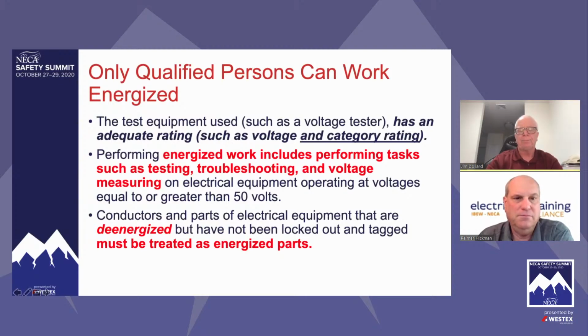Yeah, and Palmer's right. We hear about that, unfortunately, with regularity. Somebody taking a 600 volt test instrument and putting it across 4160. And I investigated an incident where just that occurred. And Palmer called that piece of equipment right out. It was a 5 kV chiller. The individuals doing that work were two journeyman wiremen. They were not qualified. They were to enter a conduit into a cabinet.